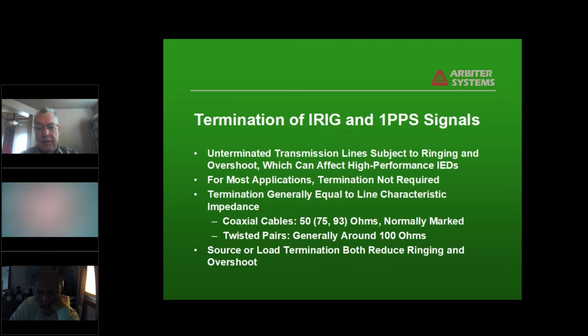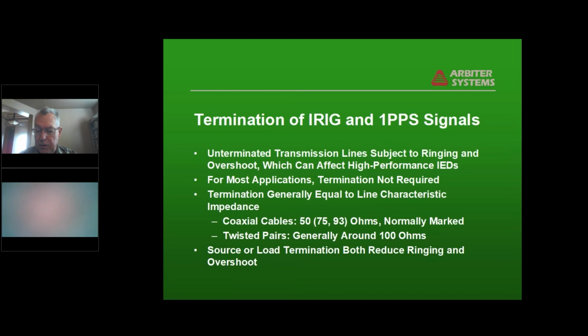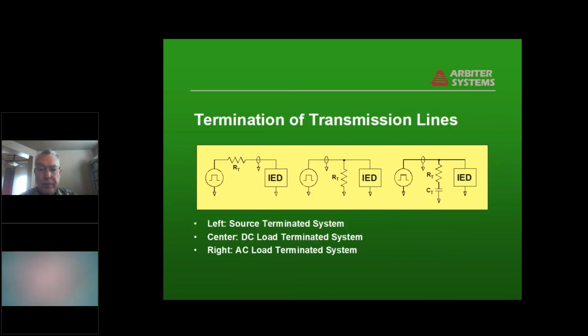Twisted pairs are normally in the range of 80 to 120 ohms, depending again on the geometry and the type of dielectric. And there's two types of termination we're going to get into, both at the source and the load, that can reduce or eliminate ringing and overshoot.